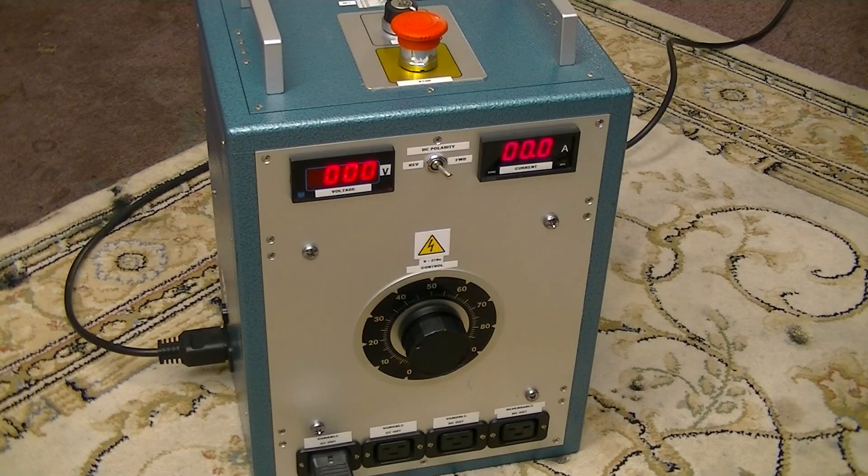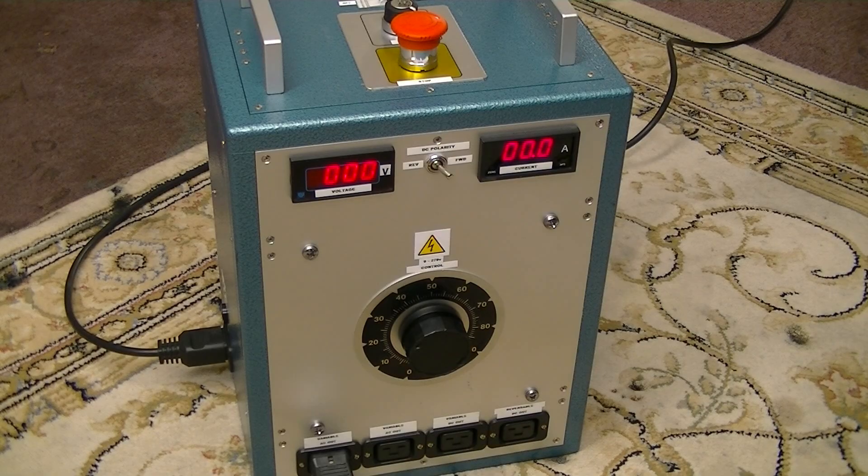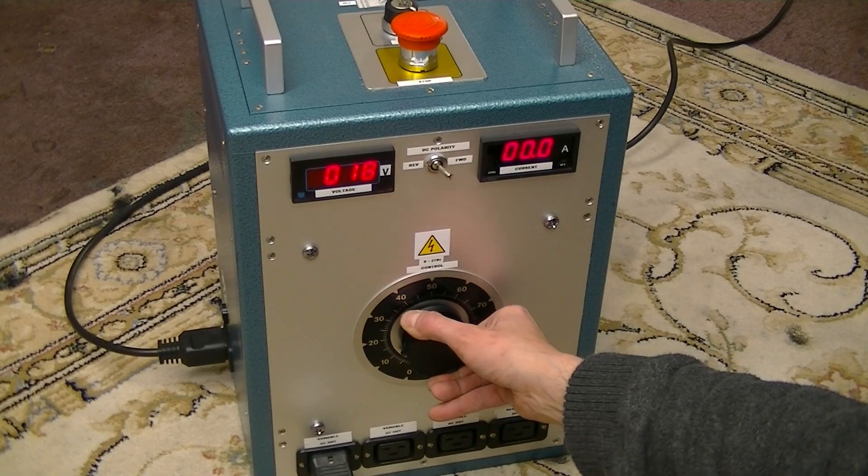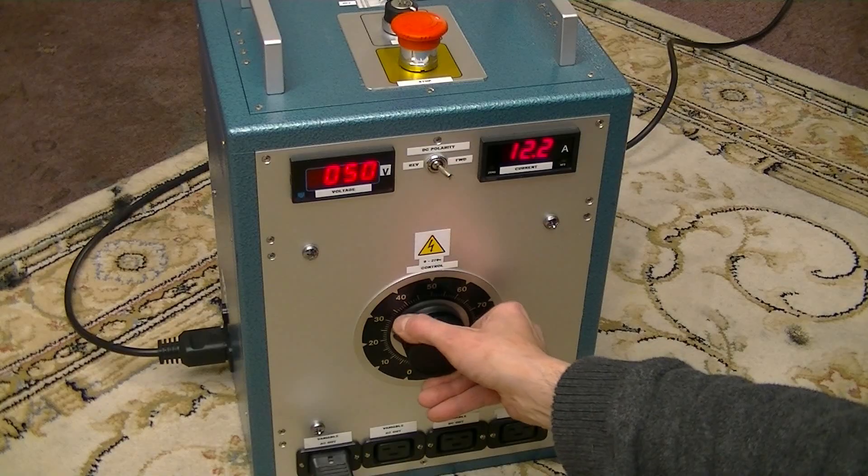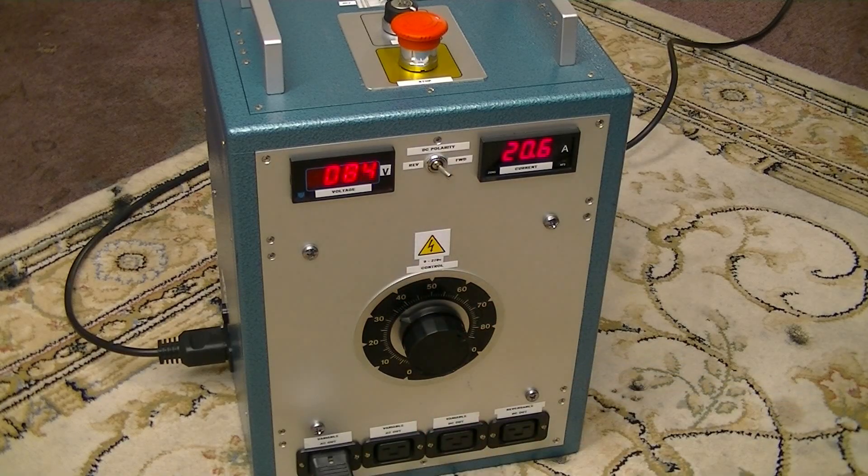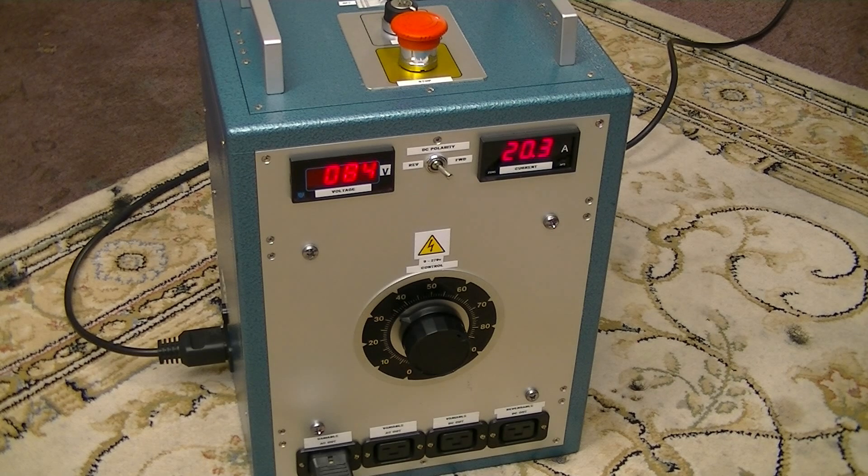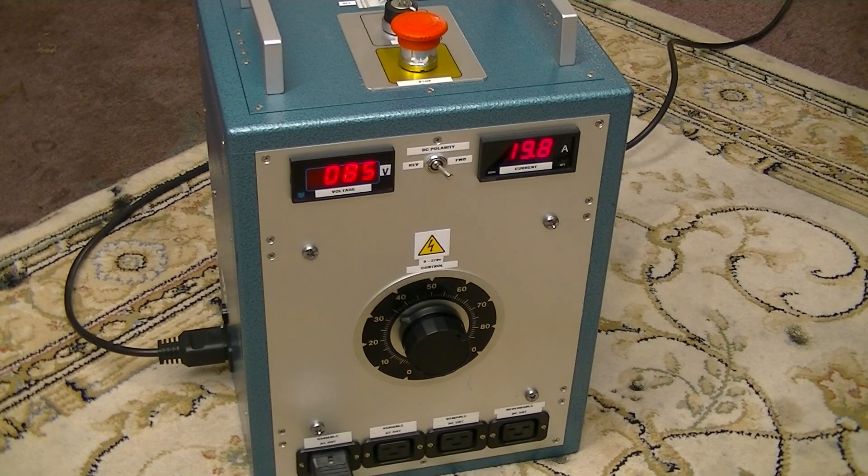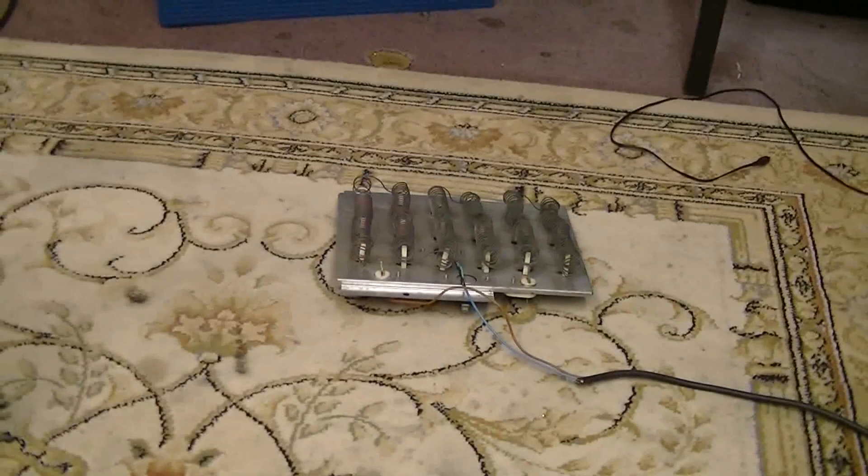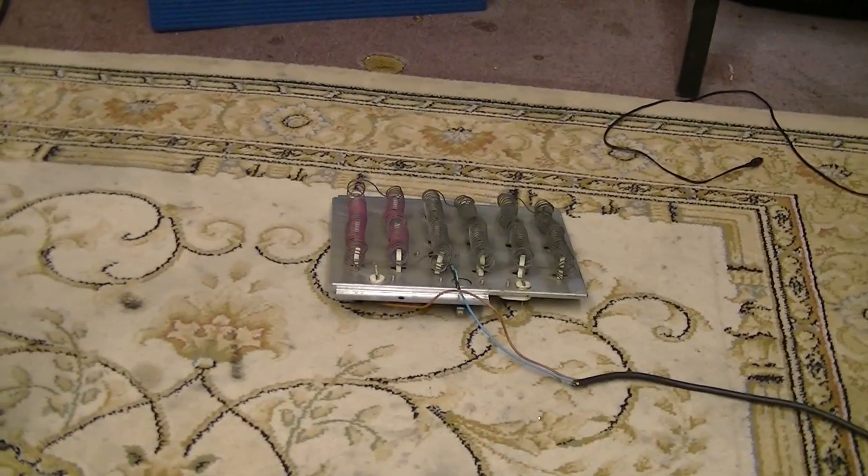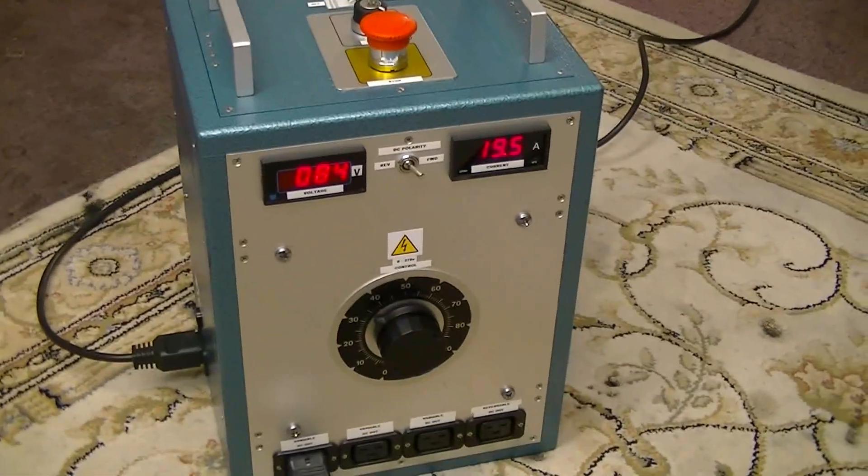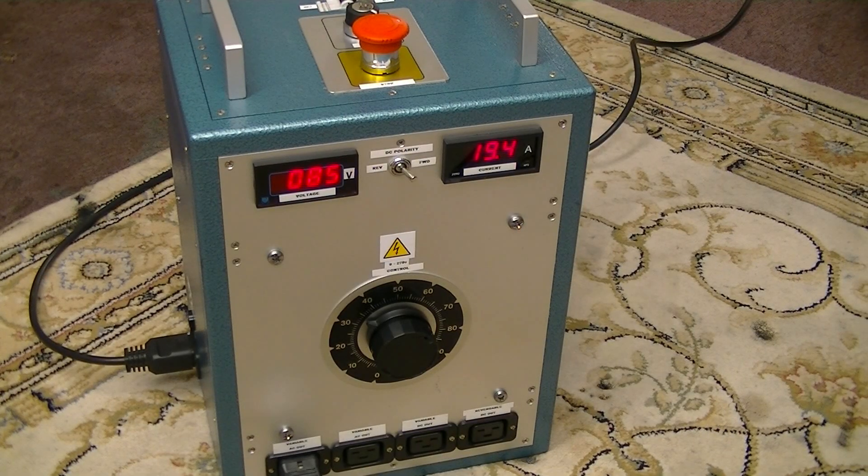What I'm going to do is I'm going to run this for a few minutes at 20 amps, just to see how we get on with that. Roughly. That's dropping slightly naturally, because that load bank, obviously it's resistive load. As that heats up, resistance increases, which causes a decrease in current. 19 amps. We'll run that for a bit. That's cooking up nicely.